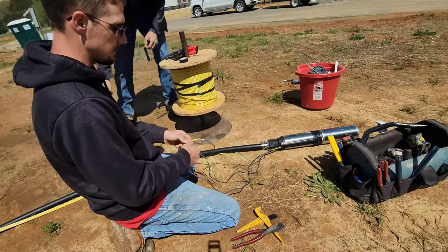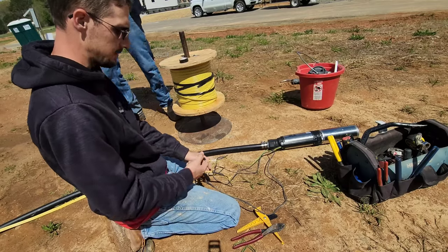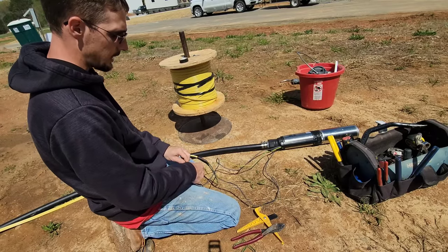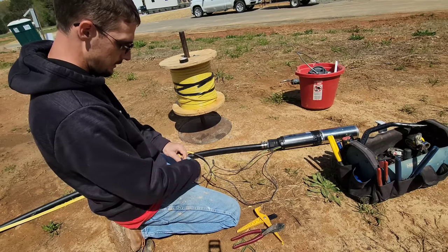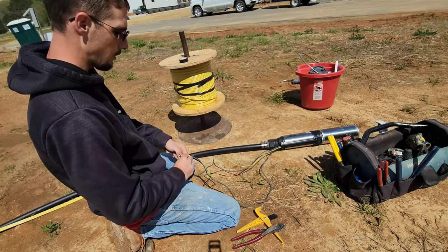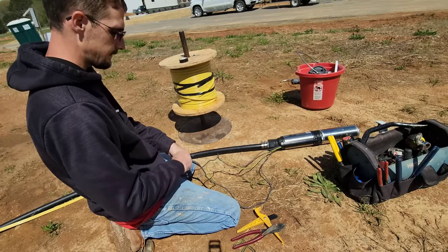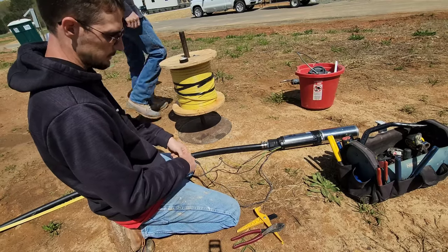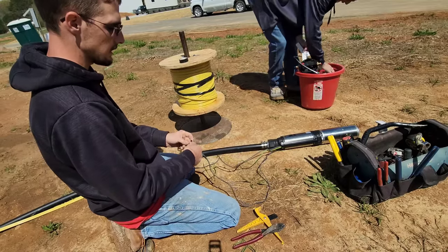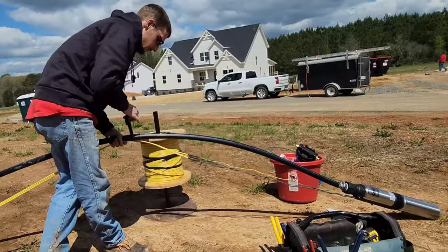About 95% of the time people reach out to me online with a two-wire system, and 95% of the time I can diagnose it correctly. With a three-wire system it's harder to diagnose because most homeowners don't have the equipment I have, and you really need to be on site. Rather than five possible situations, you could have eight possible situations, and you really need multimeters and special meters to test everything.